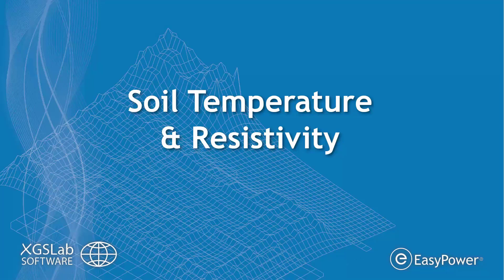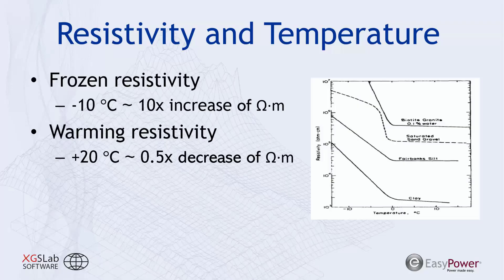Let's look at how temperature relates to soil resistivity. The temperature of soil can dramatically affect its resistivity. For example, if you measure a sample of clay just above freezing, then test that same sample 10 degrees Celsius colder, you could see a resistivity increase of 6 to 10 times on just that 10-degree swing. On the warming side, increasing soil temperature by 20 degrees could reduce that layer's resistivity by up to half, depending on the material.